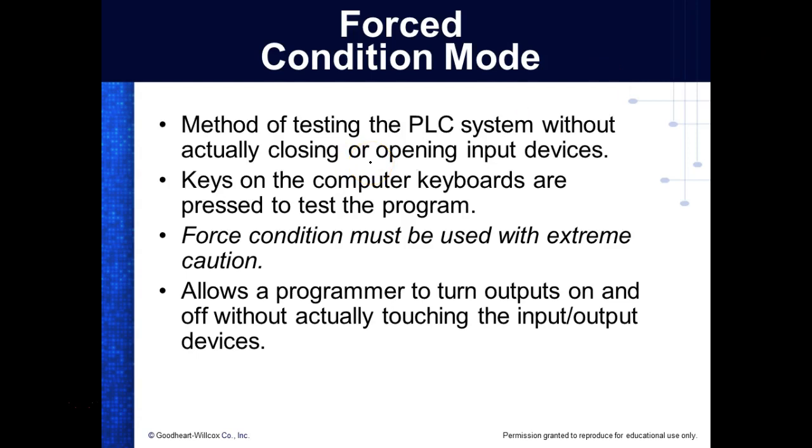So forcing, we use that for troubleshooting. We could force inputs, which means I could verify a program runs before I actually hook it up, right? Y'all understand that? So we could actually do that, not even have any input devices up. I know what each one of those bits do, and I could force them on and off.